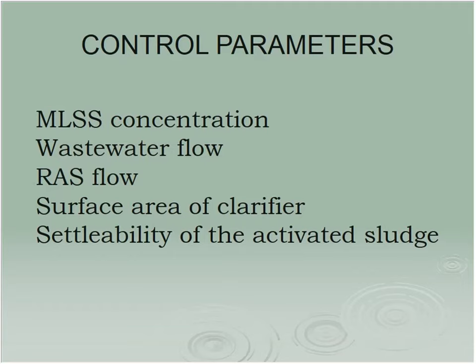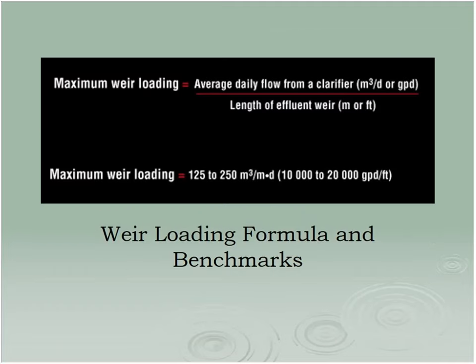Certainly, flow is a big factor. It affects your detention time and currents. Your return sludge flow can affect things by how deep you let that sludge blanket go and how much you pull down. Then there's the surface area of your clarifier, over which you have control. And how settleable is your sludge? If you've got filamentous, well, then you've got some issues.